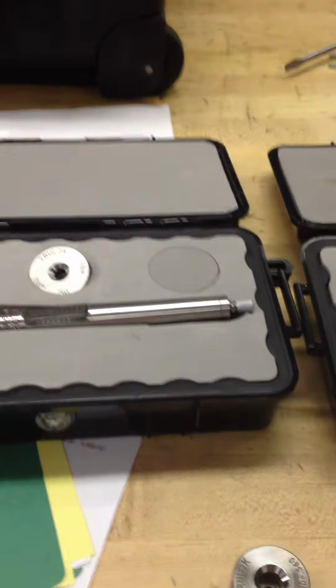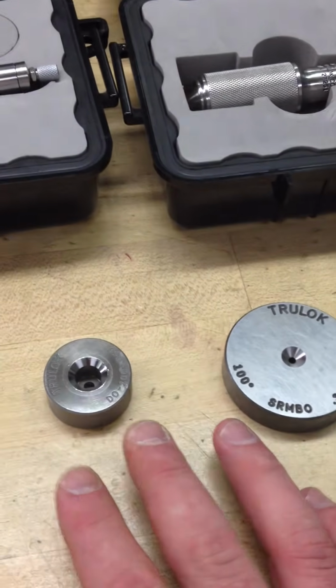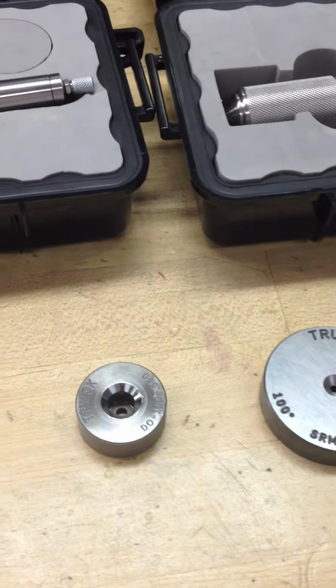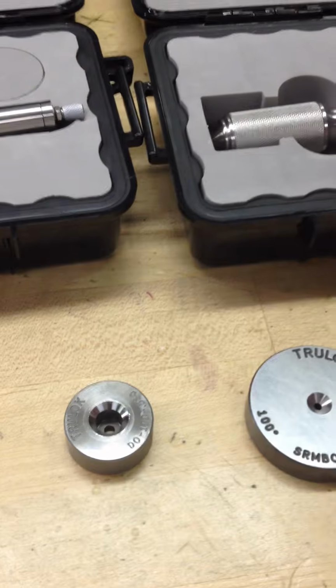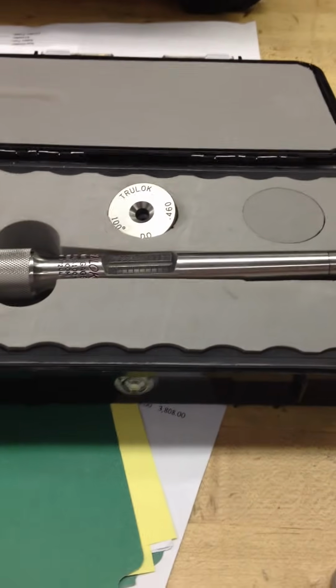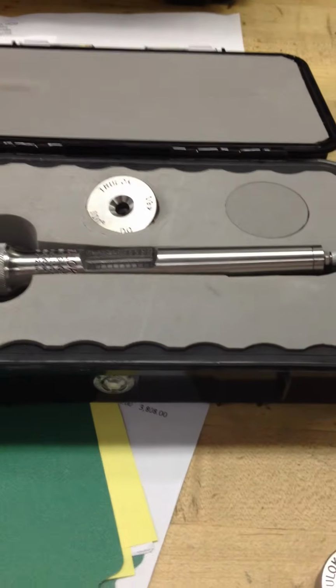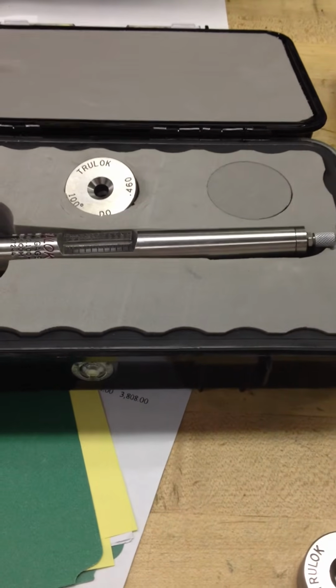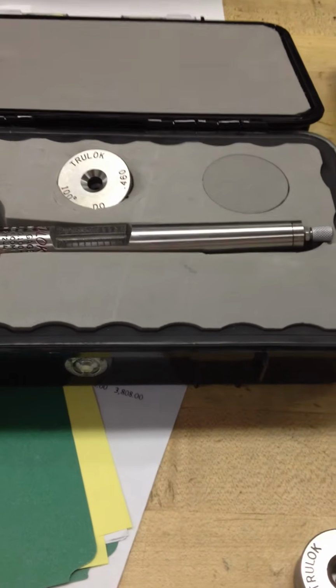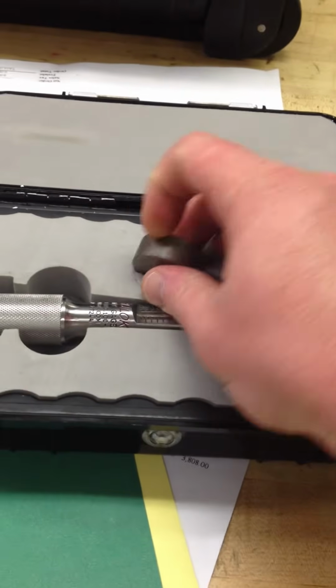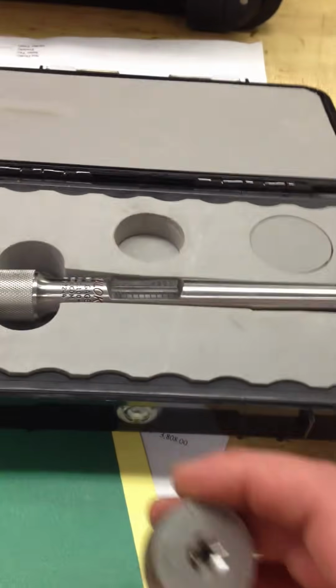You'll never be able to do a conversion that will give you an accurate reading unless you have master calibration blocks that are cut to the exact size of the measuring range on these gauges. So these gauges are 100 degrees. The bottom side of the travel or the range on this gauge is 360 thousandths. The top side is 560 thousandths. These are issued with a 100 degree by 460 thousandths set block.